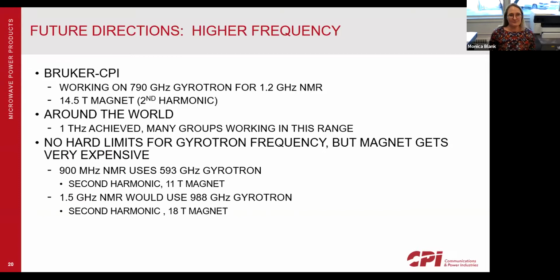As one example, unfortunately, we don't have a complete design, so I can't show anything, but at Bruker and CPI, we're working on a 790 gigahertz gyrotron for their 1.2 gigahertz NMR. And one critical part is the 14.5 Tesla magnet. We are working at the second harmonic. And there has to be a negotiation between the gyrotron makers and the magnet makers. The gyrotron people would like a 1 centimeter long flat field in a, let's say, 10 centimeter long cryostat with a 10 centimeter diameter warm bore. And the magnet people cannot do that. They would like a 1 meter long magnet with a 1 millimeter bore. And so we have to have a big round of compromise and negotiations to figure out some overall system that will work for both parties. We both have to give and try to push ourselves to the limits of our technology.